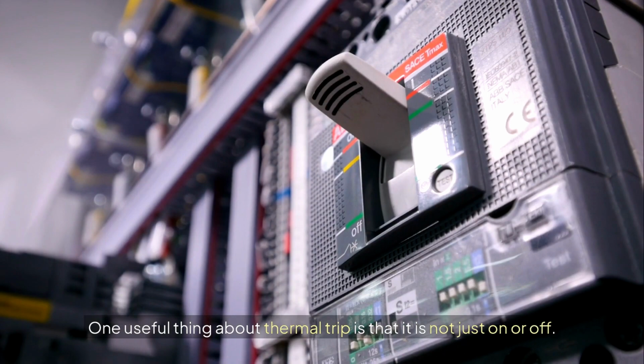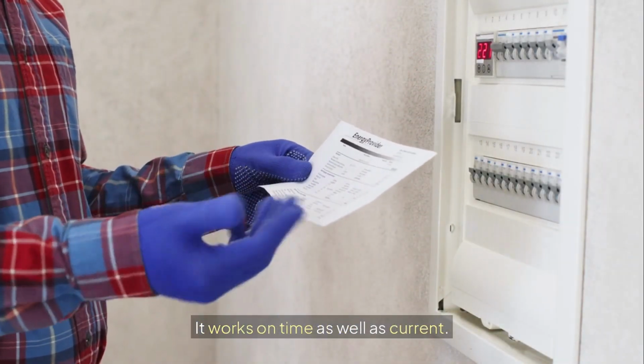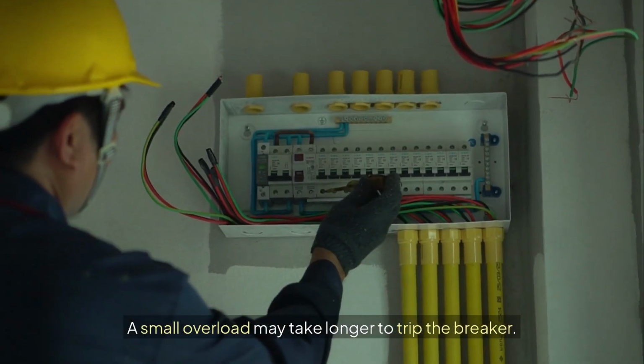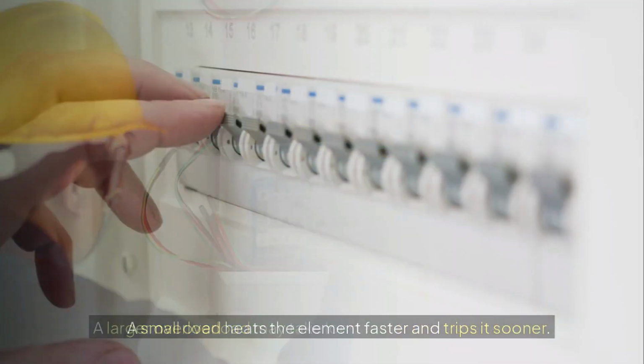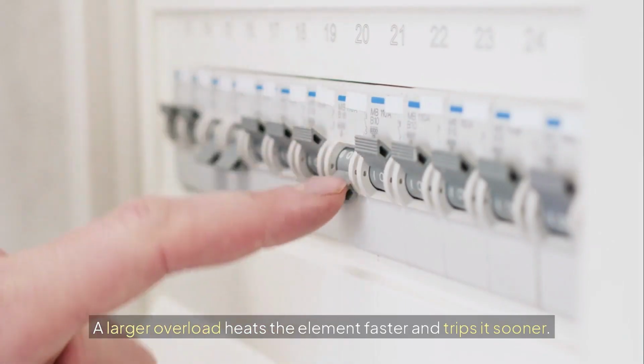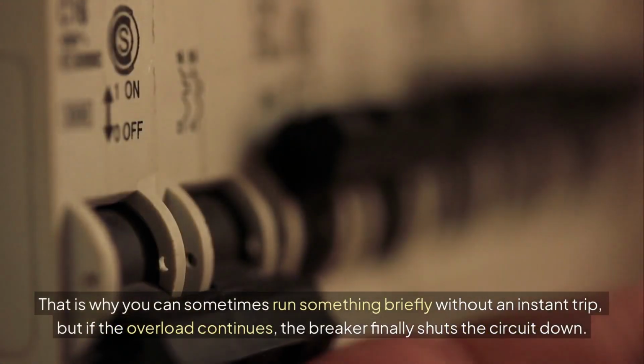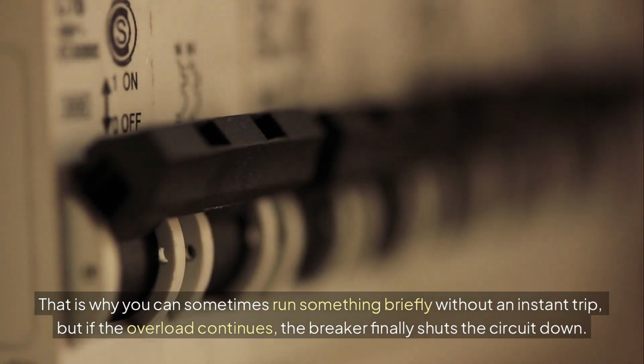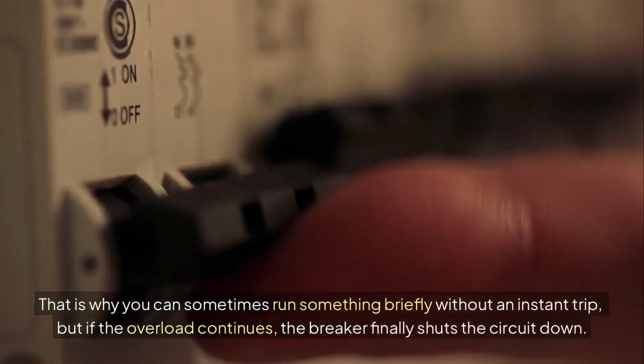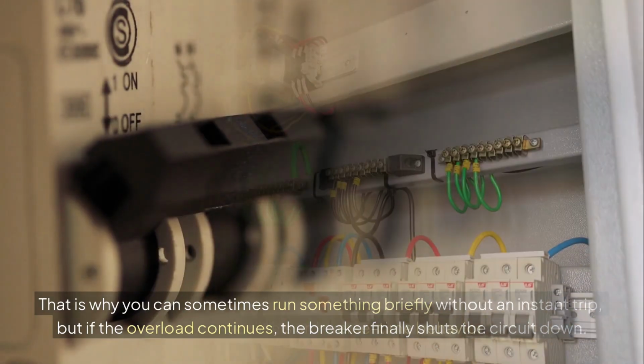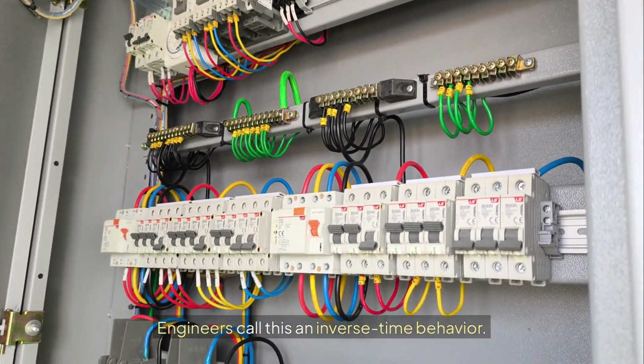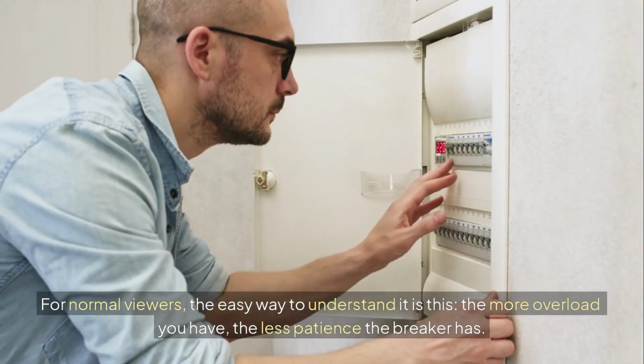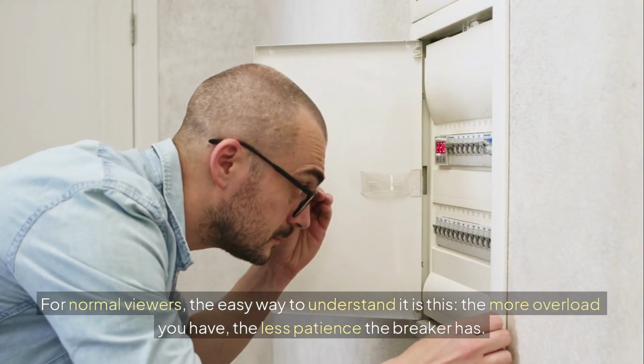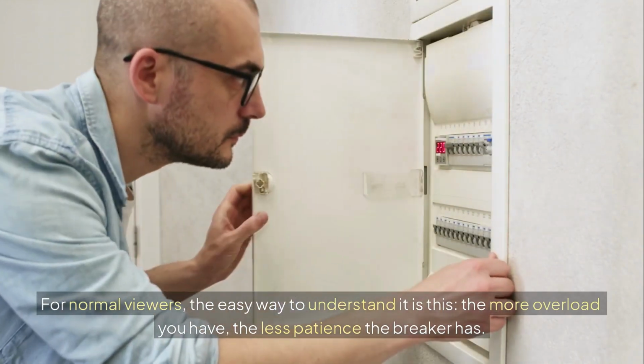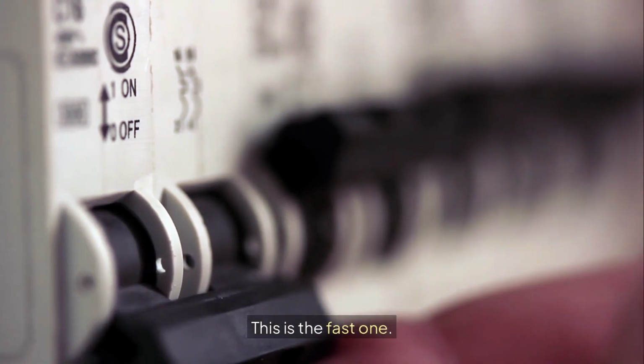One useful thing about thermal trip is that it is not just on or off. It works on time as well as current. A small overload may take longer to trip the breaker. A larger overload heats the element faster and trips it sooner. That is why you can sometimes run something briefly without an instant trip, but if the overload continues, the breaker finally shuts the circuit down. Engineers call this an inverse time behavior. For normal viewers, the easy way to understand it is this: the more overload you have, the less patience the breaker has.